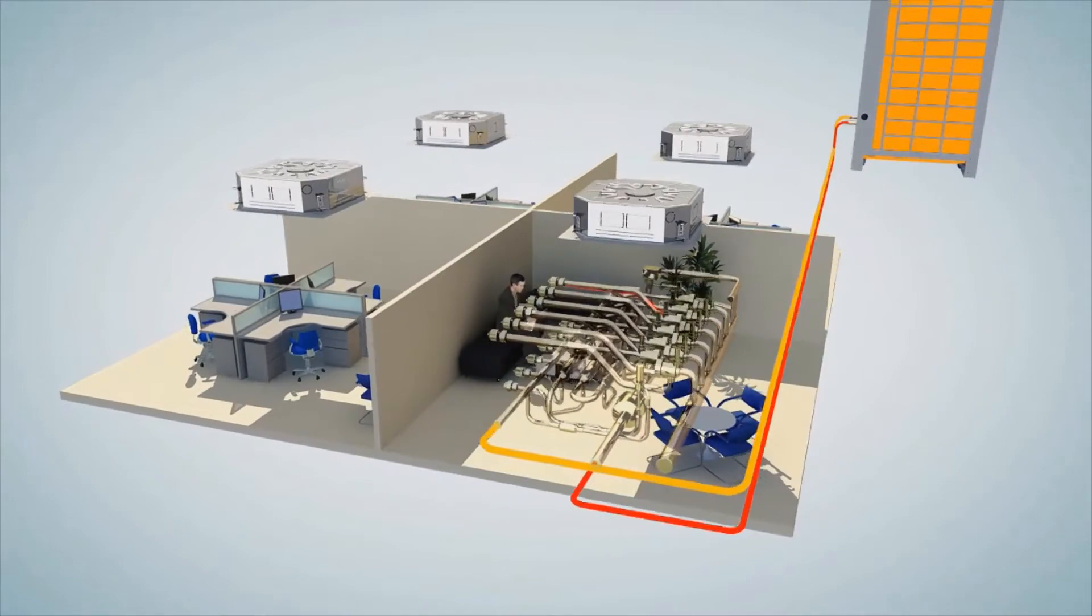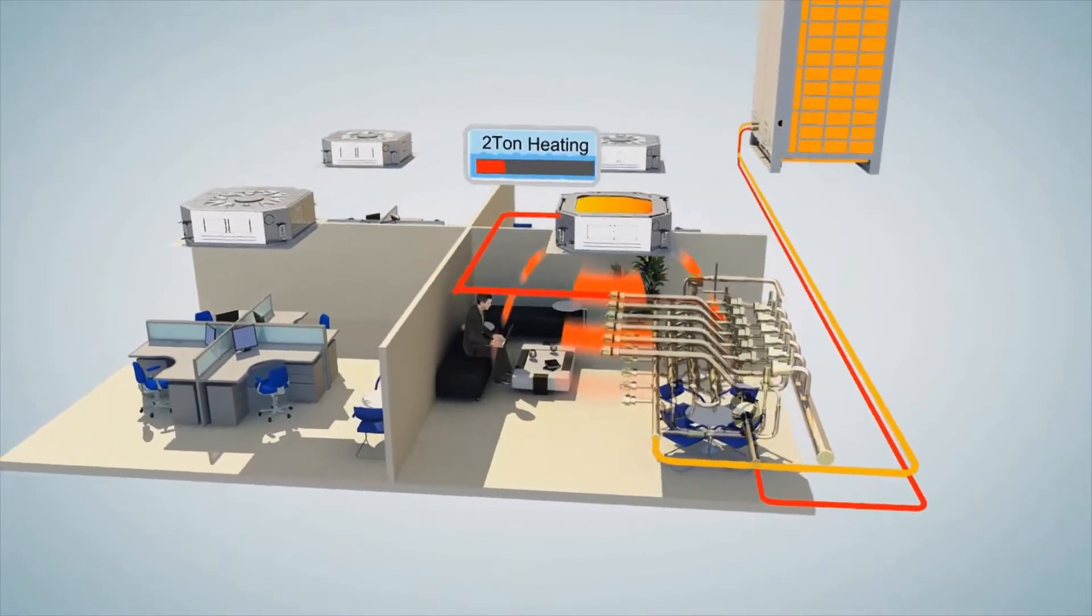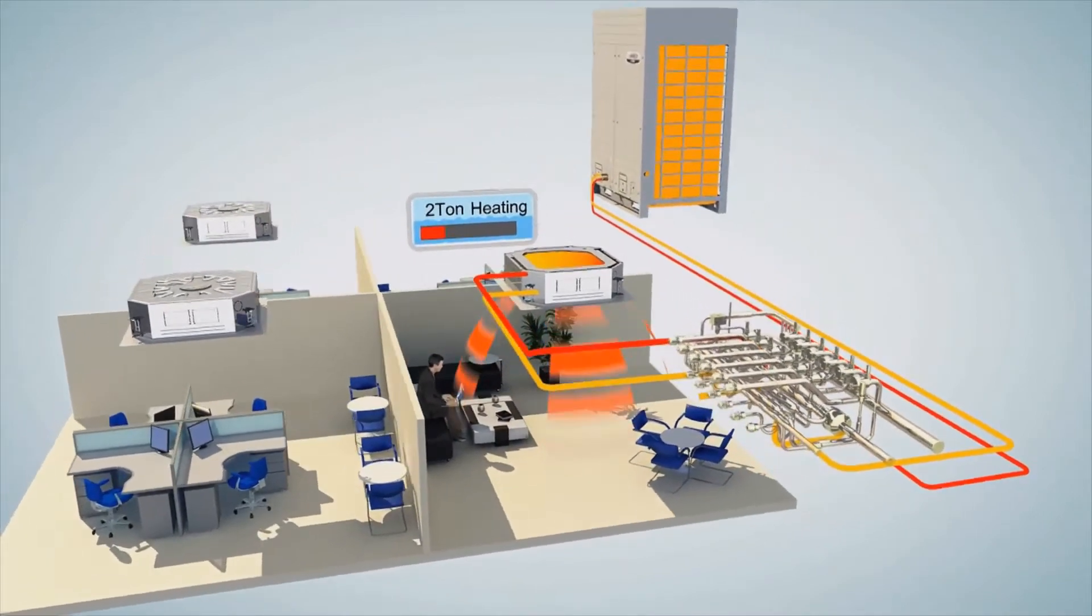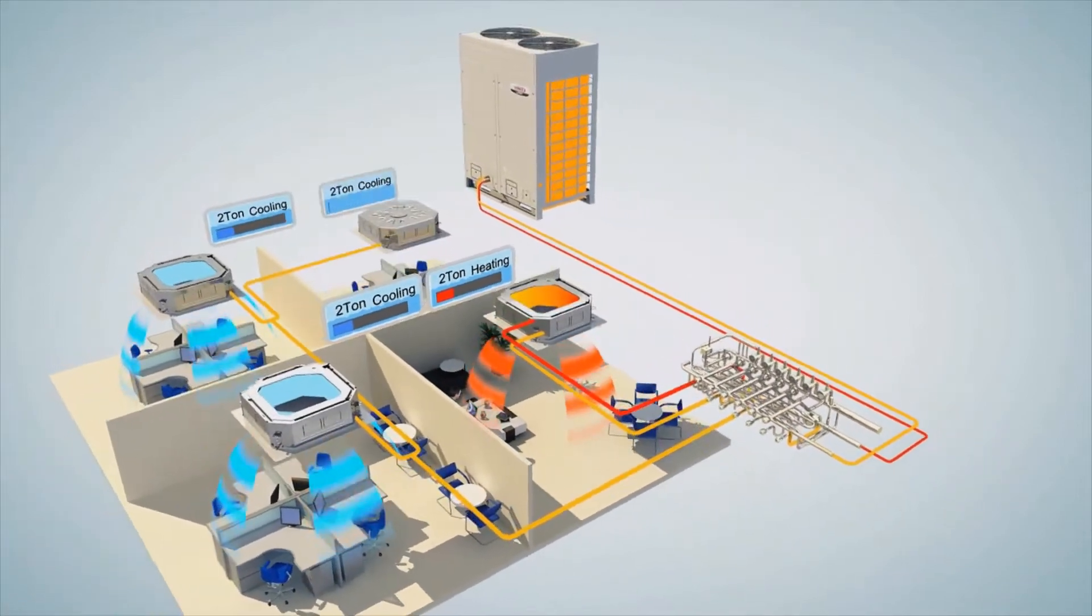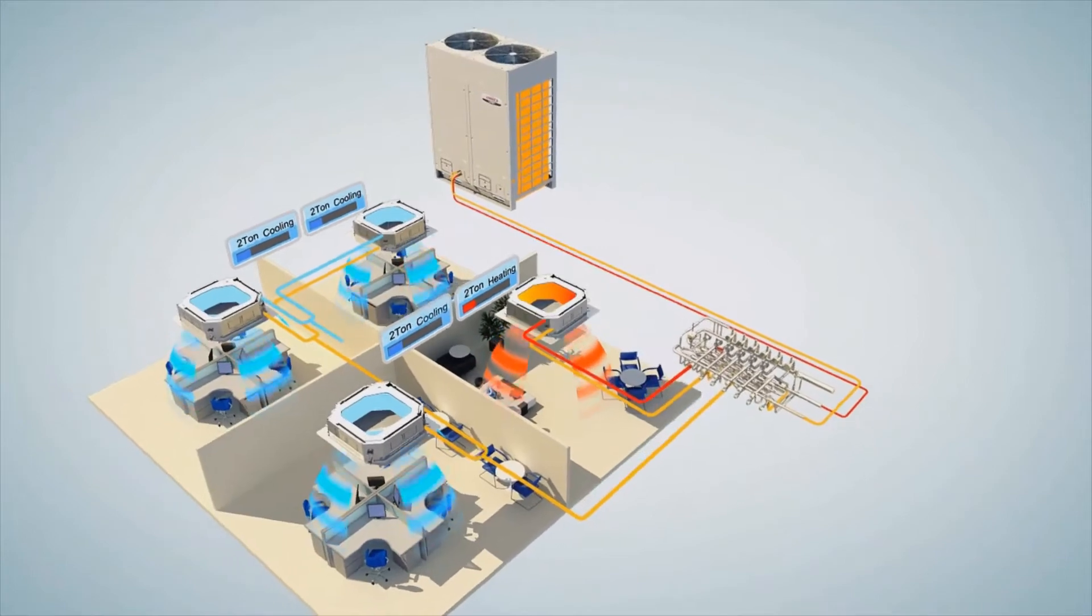During simultaneous cooling and heating mode, hot gas flows into the indoor units in heating mode, then the condensed refrigerant is directed to indoor units that require cooling. This is the basis of heat recovery.